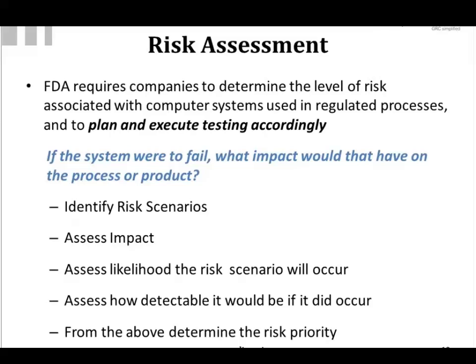Now, risk assessment is very important because the FDA realized they don't have enough resources to go out and look at every company and every GXP system in the company. So what they have asked industry to do, probably in the last dozen years, is to come up with your list, your inventory of GXP systems. And these should be categorized by risk. So whichever ones are the ones that are going to be most critical to your operation, and if they fail, would pose the most risk, those are the systems that you have at the top of the list.